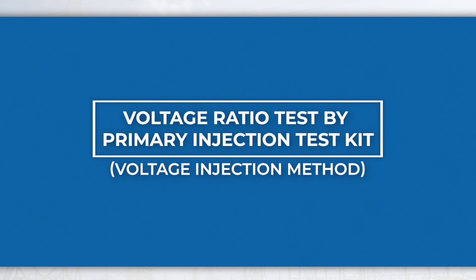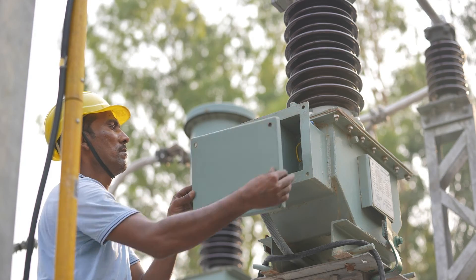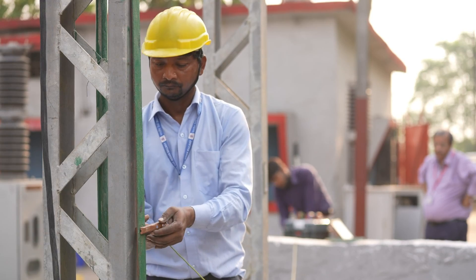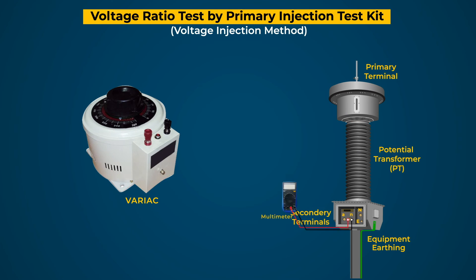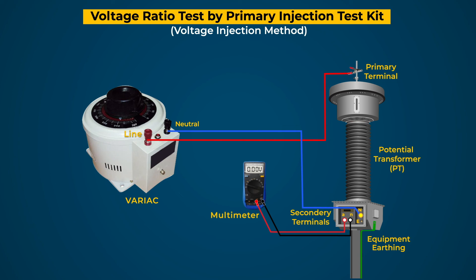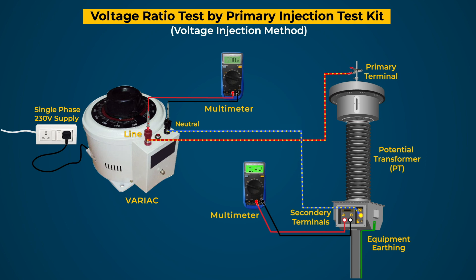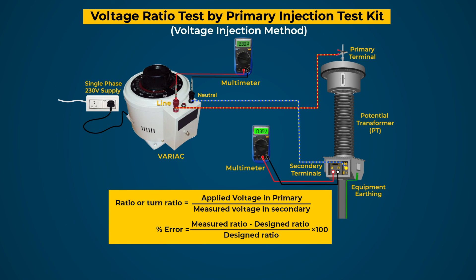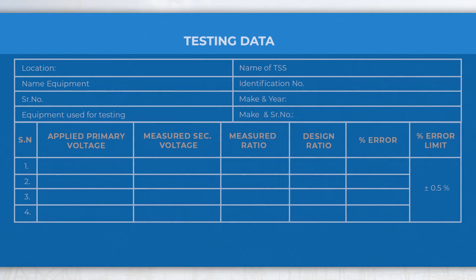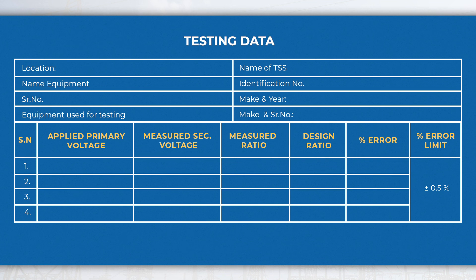Voltage ratio test by primary injection test kit (variac method): This test method is generally followed at sites on railways. Connect the AC voltmeter at both terminals of the secondary winding. Then connect the output terminal of the variac to both primary terminals and connect the AC voltmeter across the variac. Connect the single phase 230 V AC supply and apply the test voltage across the primary terminals. Check the induced voltage in the secondary winding by voltmeter and calculate the ratio and percentage error of the PT using the formulas. If the ratio error is found beyond the permissible limits, take corrective actions. Testing data may be recorded in this format for further investigation and future reference.